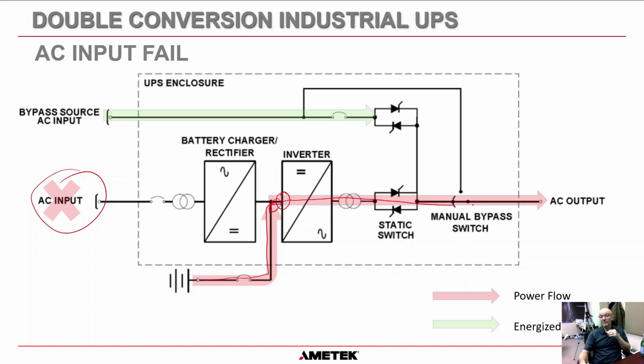And then everything else remains the same. The load circuits don't see any change whatsoever. The inverter still converts that DC back into AC. This static switch still remains on. This manual bypass switch is still in this position. And everything is as if there isn't a power outage, except the charger is not working anymore.